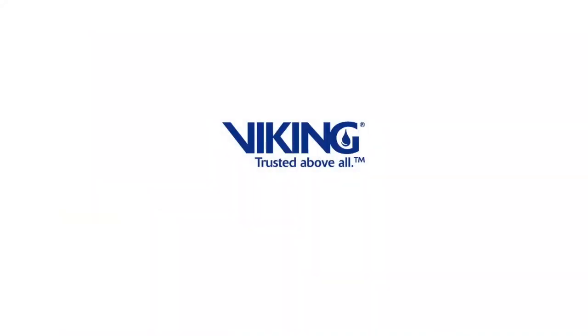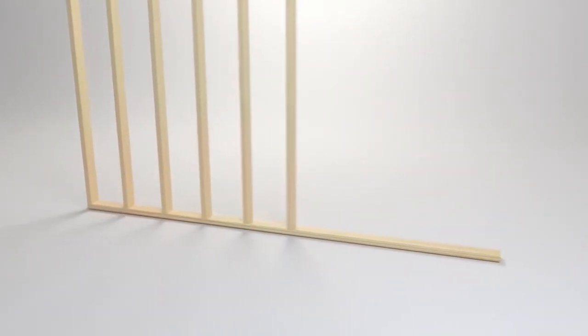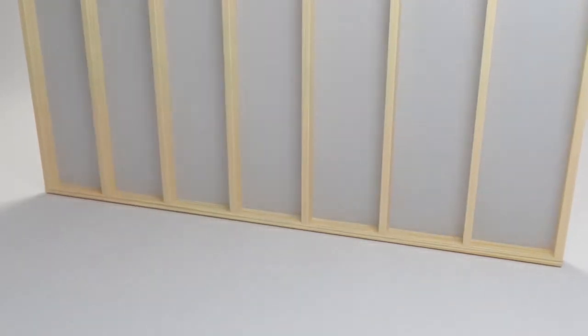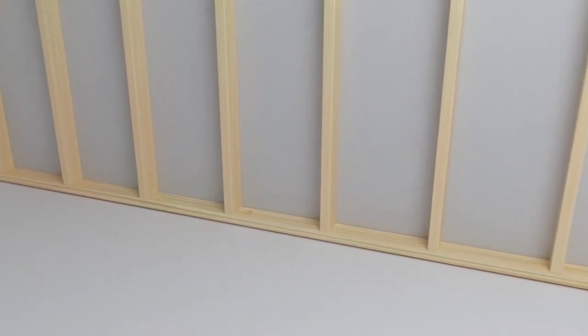Okay. All righty. I'm working on an NFPA 13D project now, this questioner asks, and the construction is 2x4 walls. The customer wants a flat plate concealed sidewall sprinkler installed. Is this even an option that Viking offers? Yeah, as you can see playing behind us in the animation here, what we have is our VK480 sidewall sprinkler.